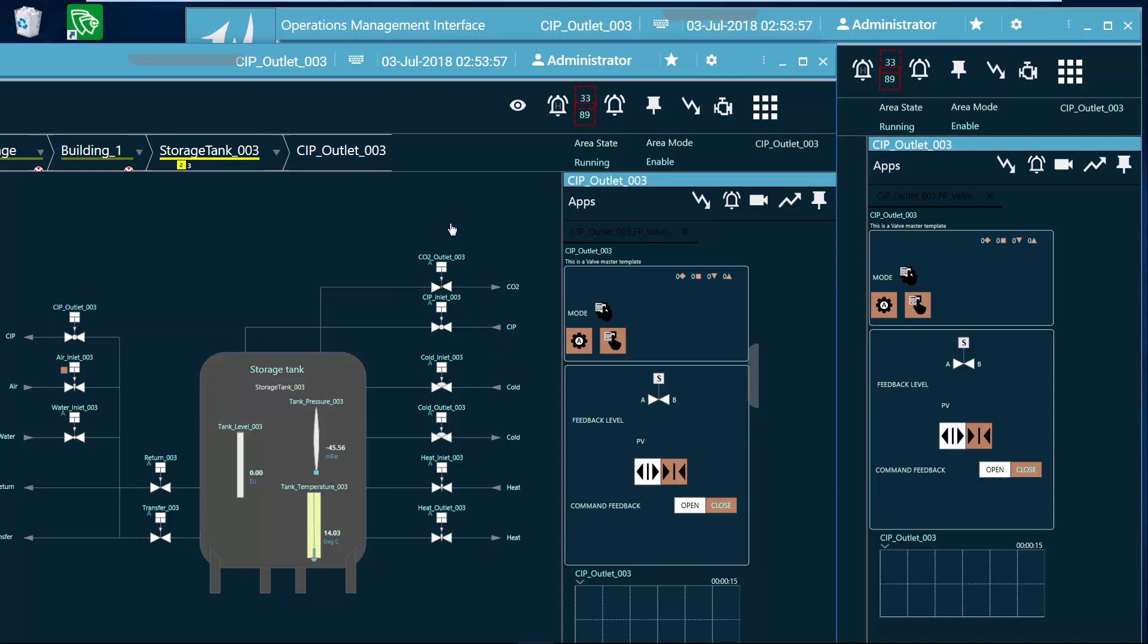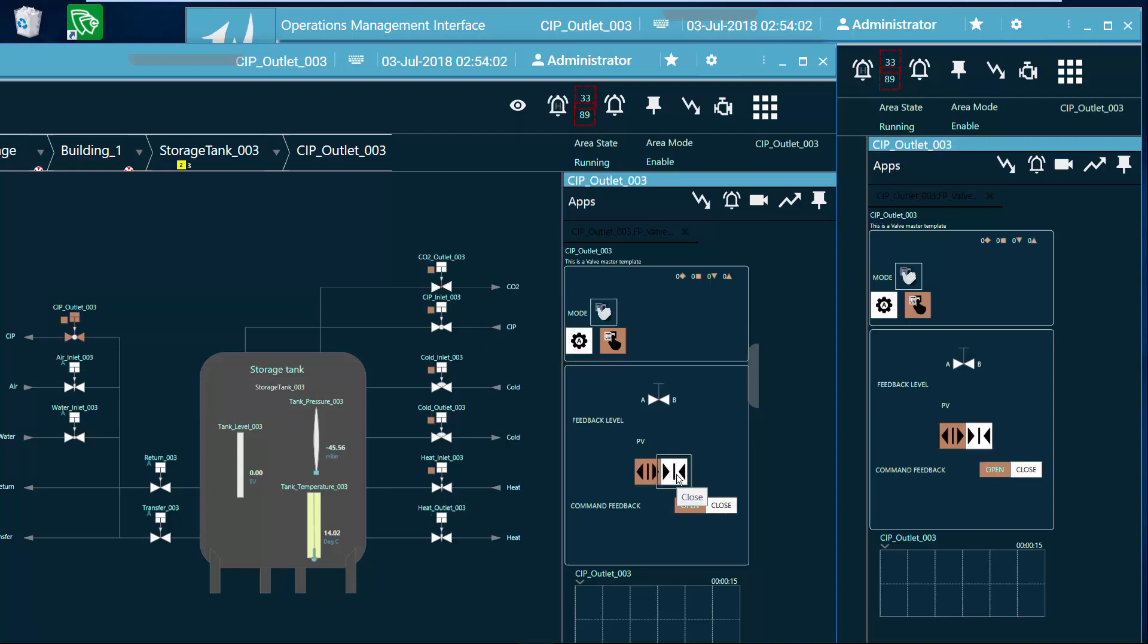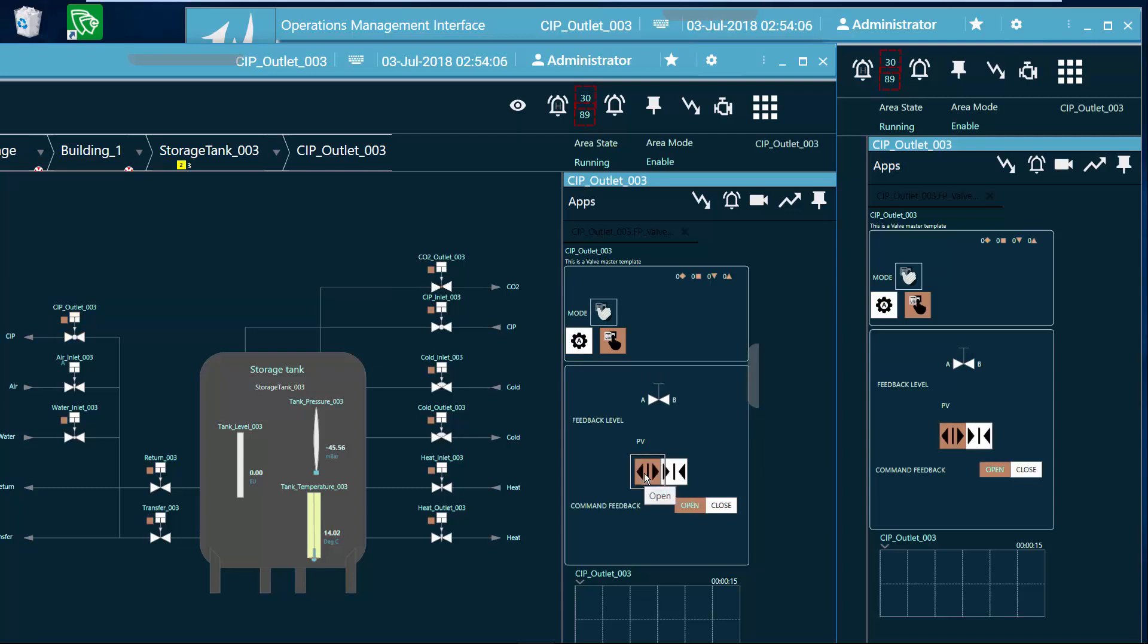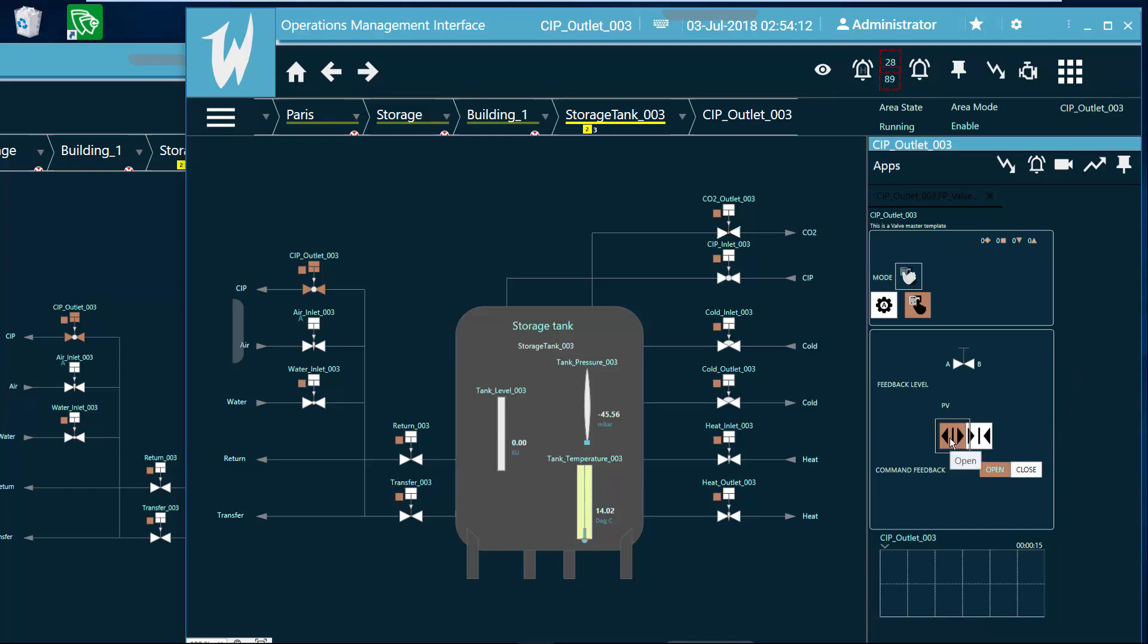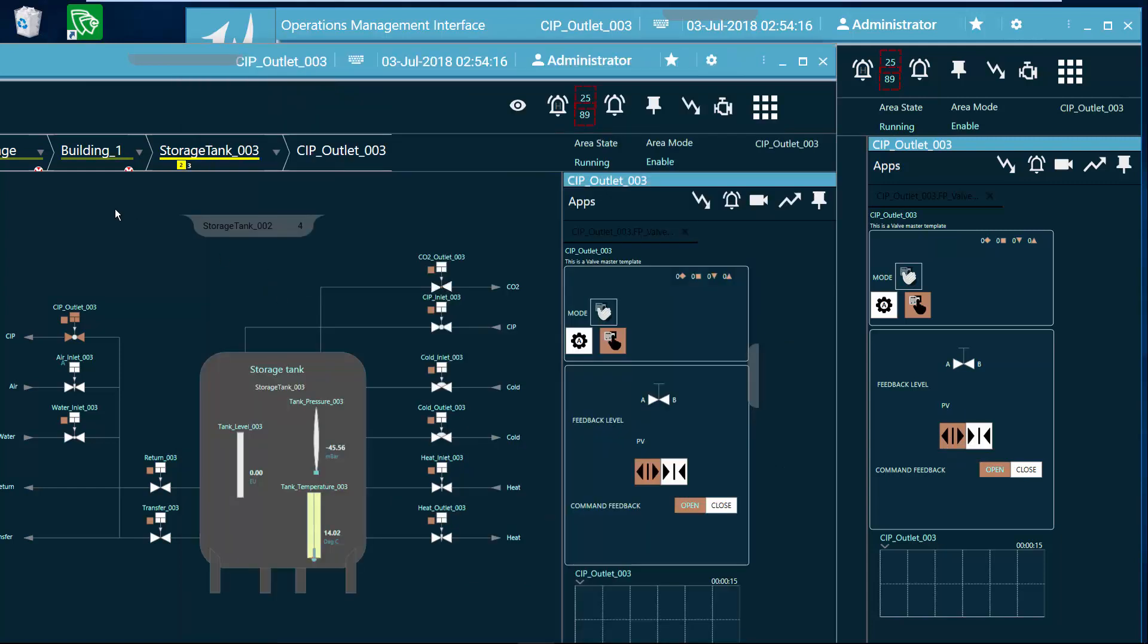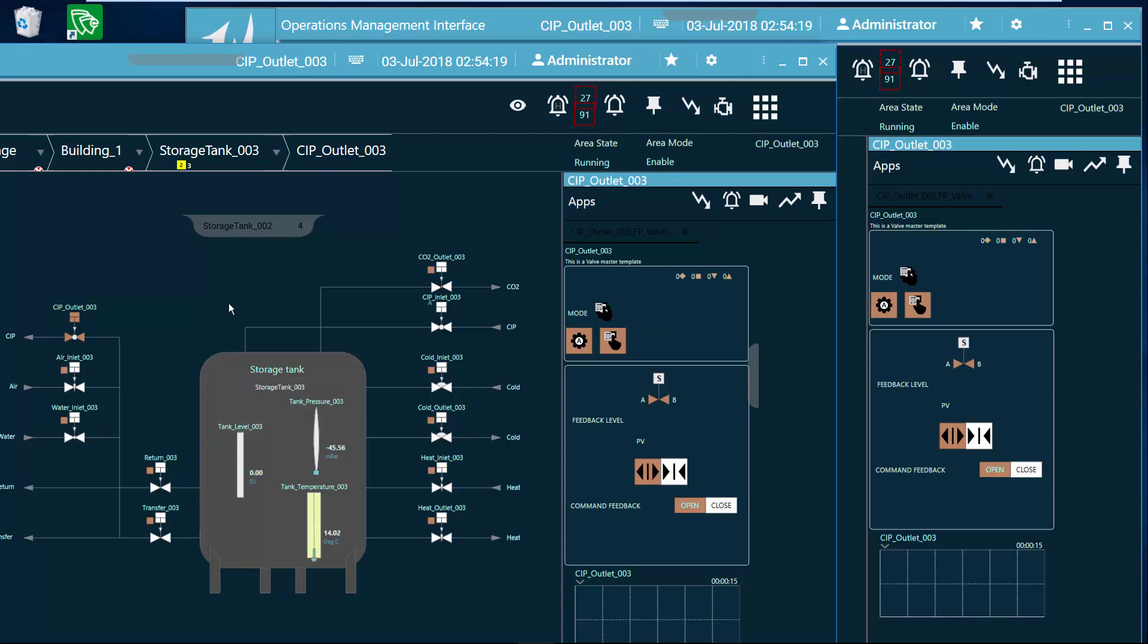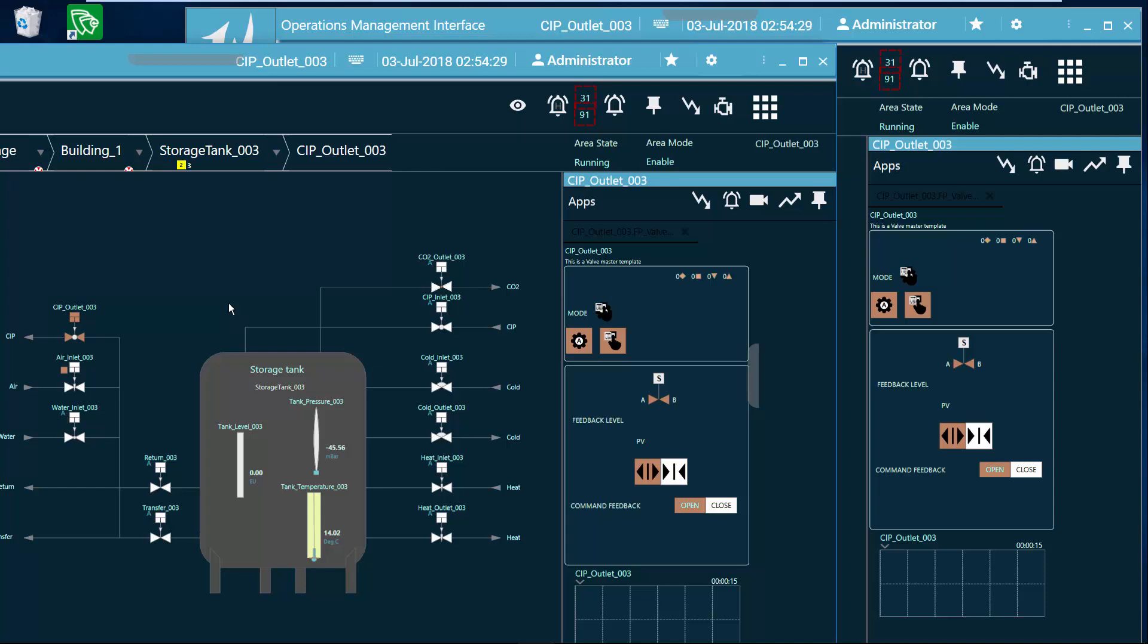But the top view here is I have the read-write application running, and I still have the ability to go here and open and close the valve. You can see the status changes on the background of the read-only application. So the read-only application is running in this window, but I can't control it. If I try to open and close that valve, there is no control. Just trying to demonstrate that functionality of the read-write running two separate instances of the OMI application on the same screen. One was opened with the read-only flag. One was opened the normal method. One has control, and one does not.